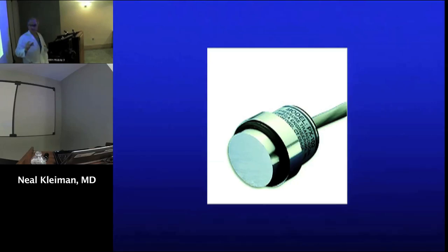So these are the two important things. If you think about it, it's like an electromagnet—well, there's nothing magnetic about it. So what happens when the heart beats? Pressure is transmitted through a catheter. The catheter is connected to a transducer—this is the transducer. So really what you have is a column of fluid extending out this way, collinear with the transducer. What happens to this device as pressure is exerted? Well, it doesn't necessarily oscillate—it gets stretched, right? That's the basic principle of a pressure transducer. It gets stretched as pressure is exerted, and as the pressure drops, it returns to its initial position.